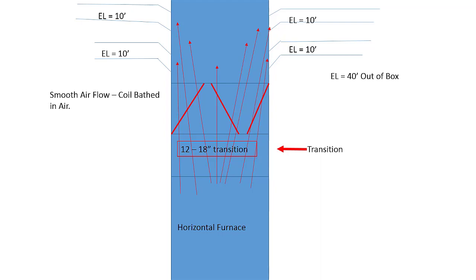And you will also notice that we have added a 12 to 18 inch transition, which allows the airflow to spread out and smooth before it enters the coil. This gives us a much smoother transition out of the furnace, through the coil, and into the ductwork.